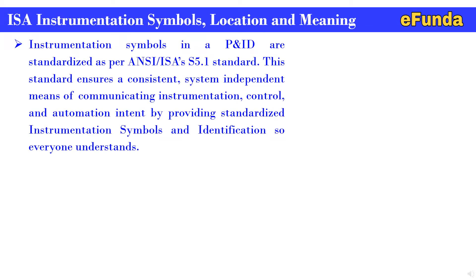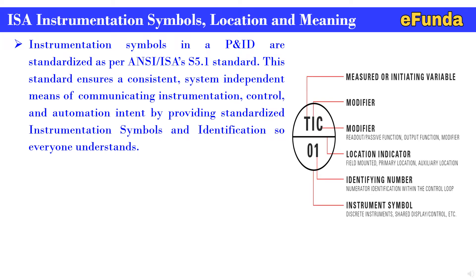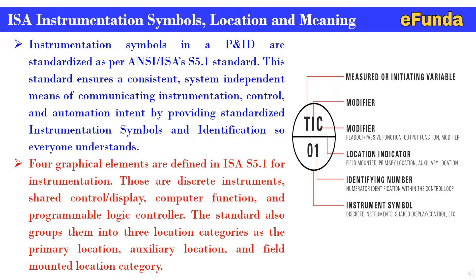ISA instrumentation symbols in a P&ID are standardized as per ISA S5.1 standard. The standard ensures a consistent, system-independent meaning for communicating instrumentation, control, and automation intent by providing standardized symbols and identification. Graphical elements defined in ISA S5.1 include discrete instruments, shared control displays, computer functions, and programmable logic controllers. The standard also groups them into three location categories: primary location, auxiliary location, and field-mounted location.